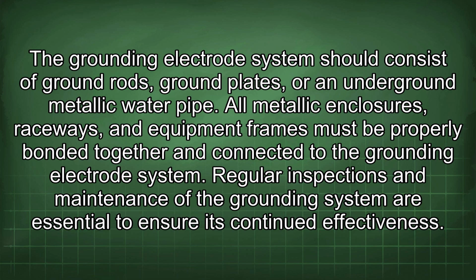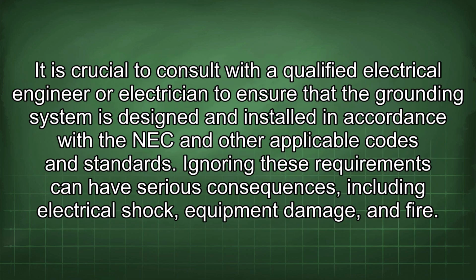The grounding electrode system should consist of ground rods, ground plates, or an underground metallic water pipe. All metallic enclosures, raceways, and equipment frames must be properly bonded together and connected to the grounding electrode system. Regular inspections and maintenance of the grounding system are essential to ensure its continued effectiveness. It is crucial to consult with a qualified electrical engineer or electrician to ensure that the grounding system is designed and installed in accordance with the NEC and other applicable codes and standards.